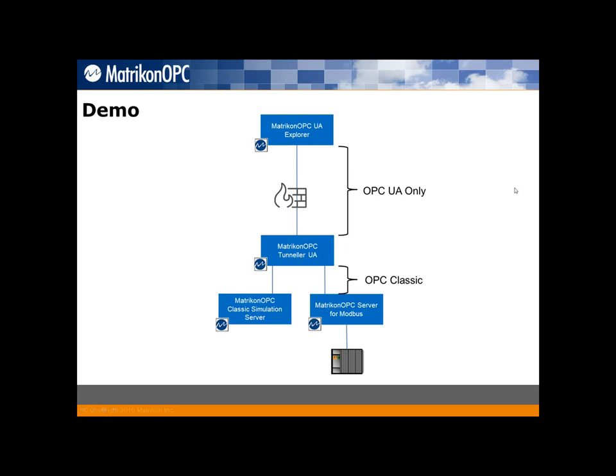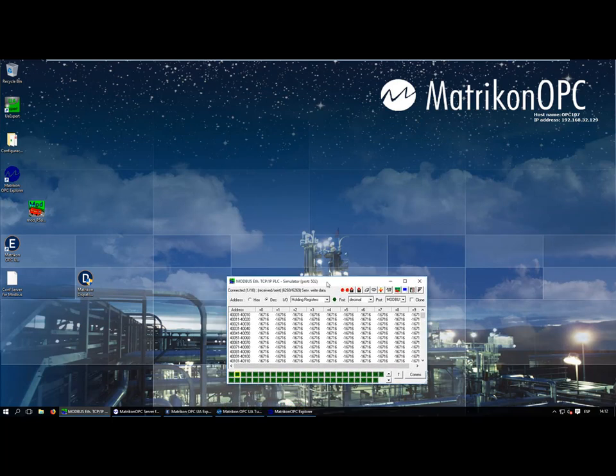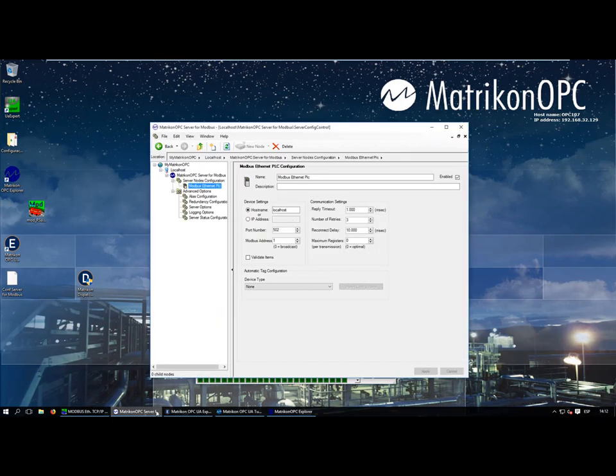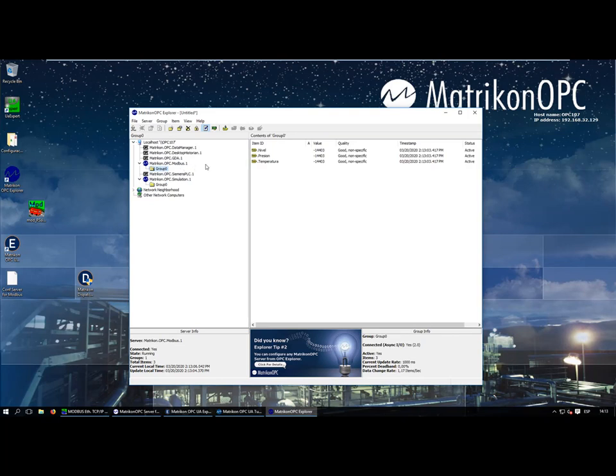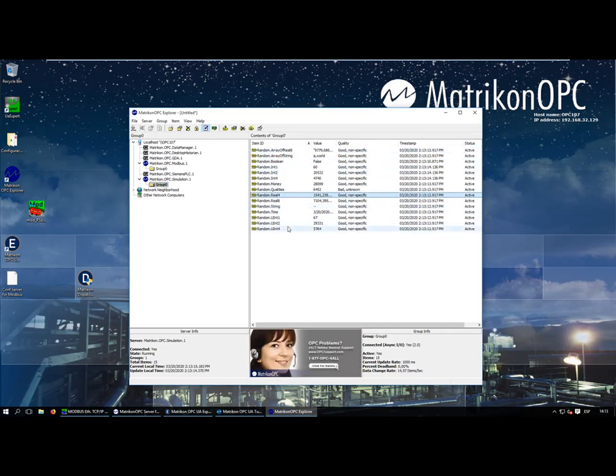I'm going to show you my virtual machine so you can follow the steps. I have the Matrikon OPC Server for Modbus connected to a Modbus simulator acting as a PLC, reading data from port 502, Modbus address 1. I also have the Matrikon OPC Simulation Server. Using Matrikon OPC Explorer as an OPC classic client, I'm reading data from both the Modbus server and the simulation server. We now want to make this data available to an OPC UA client.